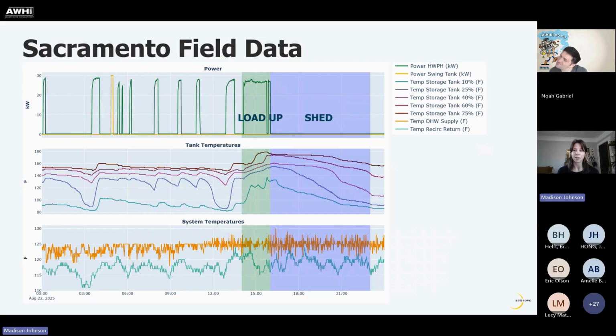So the top row of the plot, we have system power. Our heat pump water heater is in green and our swing tank is in yellow. The swing tank is disabled during shed at this site, so it's locked out during shed. As we enter our green load up period, we see the heat pump water heater turn on and stay on for most of that load up period, so it's charging up our tank. And then once we enter our scheduled shed period, we don't have any energy consumption from our heat pump water heater or our swing tank, which is really exciting. This is a super successful shed period.